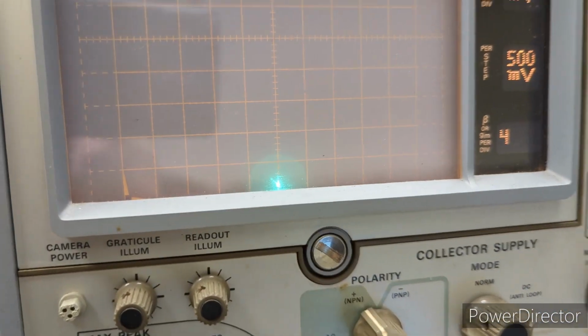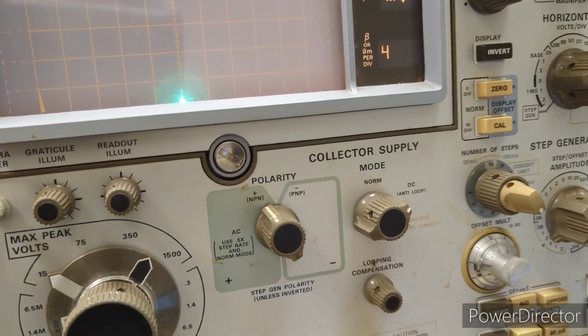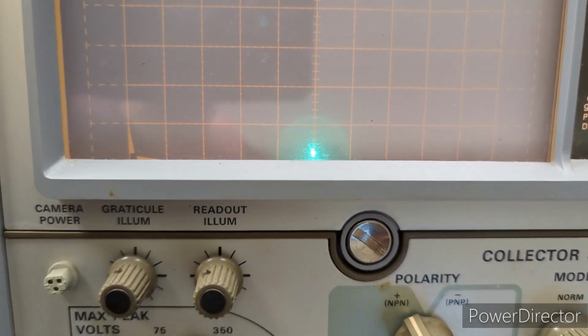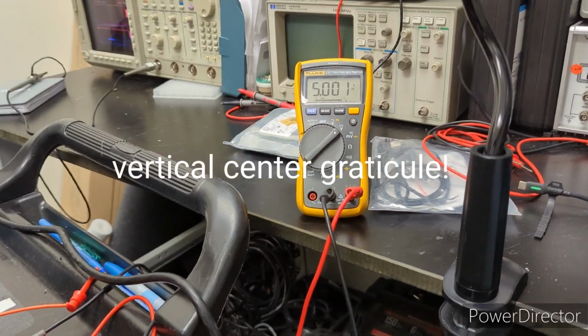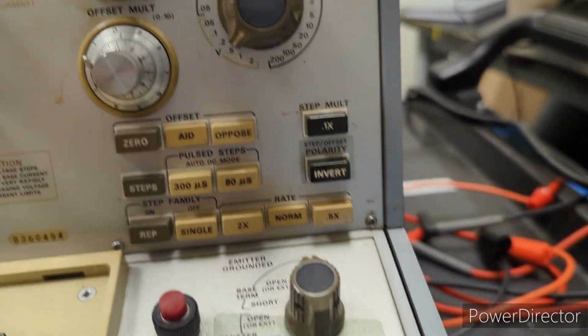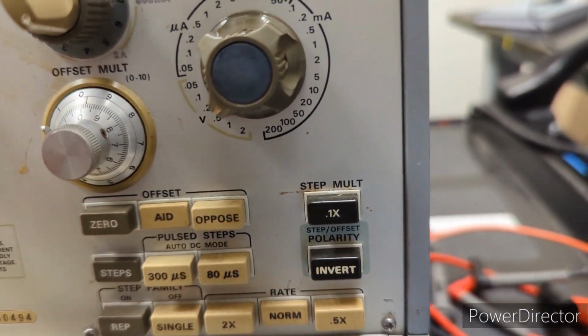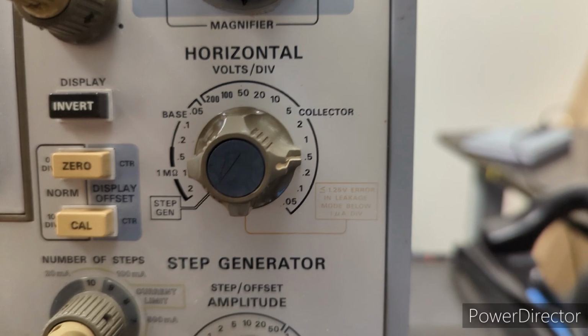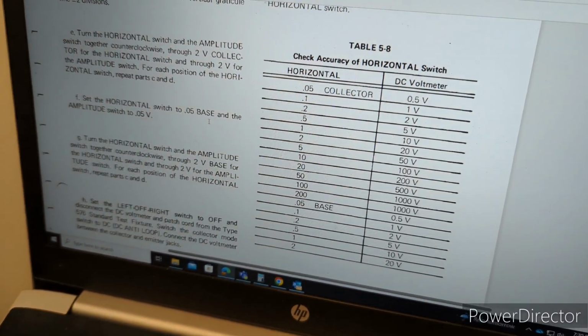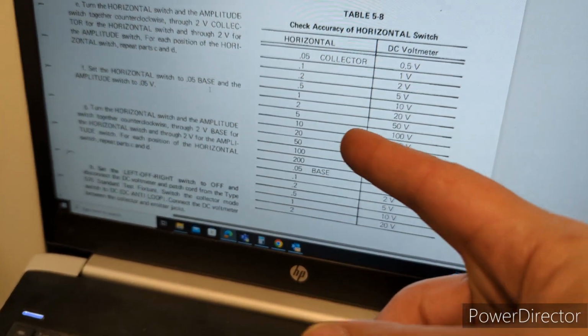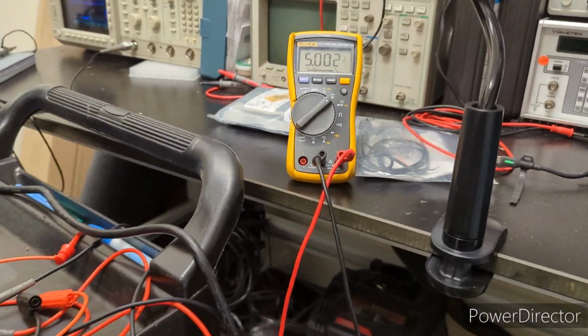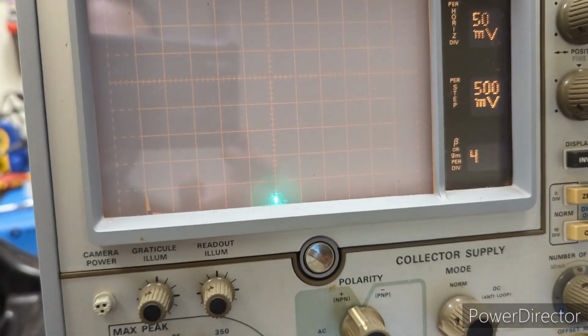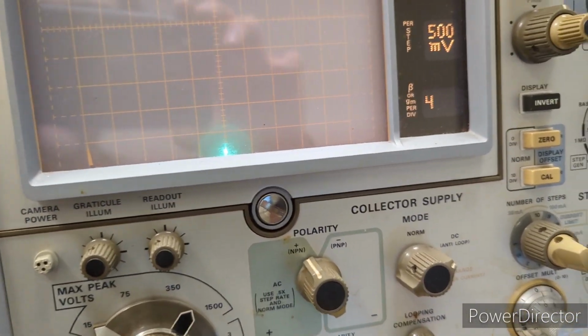Okay, so now we're checking the accuracy of the horizontal switch, which again we couldn't do correctly in the third video I did. You can see here we're centered on the CRT reticle, got 5 volts on the meter, and we have the amplitude set to 0.5, collector set to 0.5 volts, and I'm just going based off this table that's provided in the service manual. So you're going to check all those up to 2 volts, and I should get the correct voltage on the meter. So far so good, we're looking very accurate, and I'm going to continue with this procedure and keep moving forward after that.